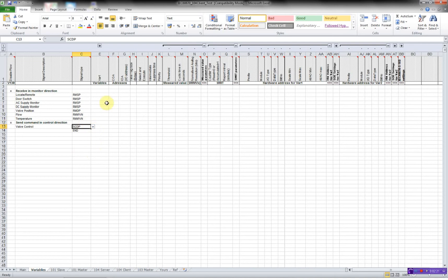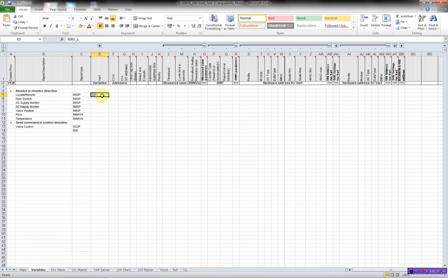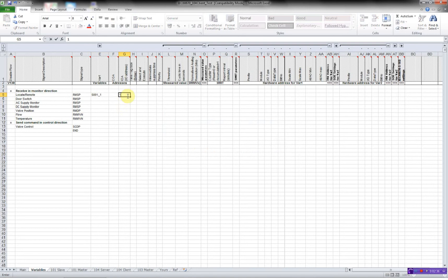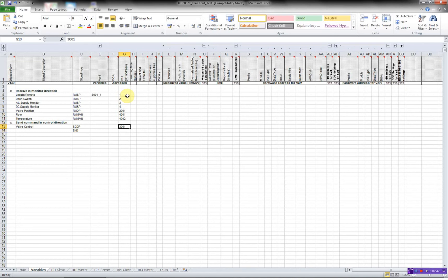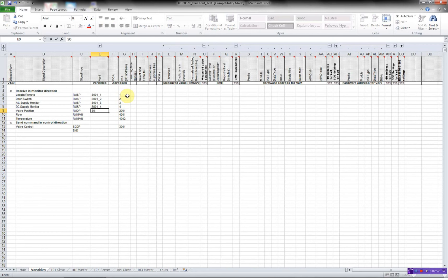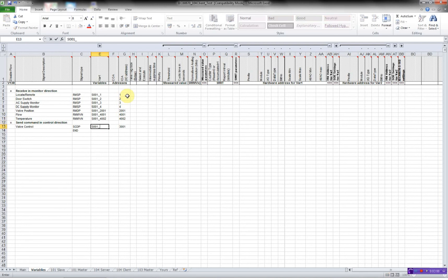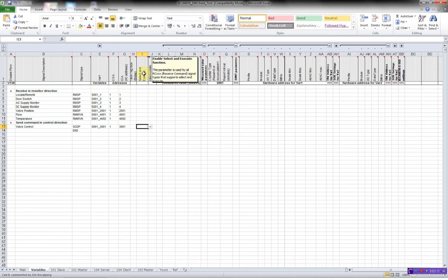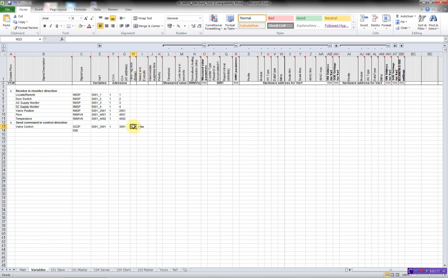Then I have to give my variable some names. I'll be using the naming convention slave 001 and then the IOA address. So I'll just fill out the IOA address. And then the IOA address is one for this. Then I have to specify whether we are using the select execute functionality. In this example we have false. Just put in 0 byte for the tag type.